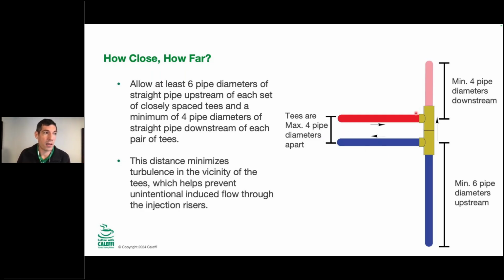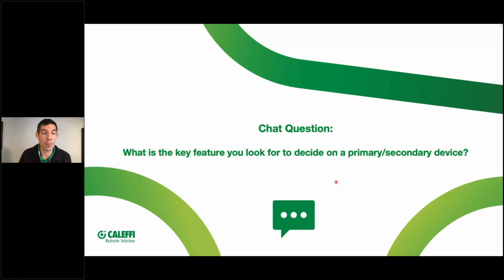Another thing that can be tricky about closely spaced tees is you do want some minimum pipe diameters upstream and downstream. This isn't to scale, but you want a little bit of calmness in the piping upstream and downstream. If you just have a 90 right here and a 90 right there, you have a little too much chaos in the center of those closely spaced tees to really let that work to keep those two flows out of conflict. So that is a limitation in piping that can come up as far as just the space that we have in mechanical rooms, depending on the pipe size that you're working with.